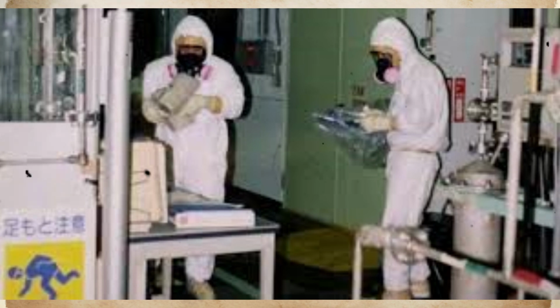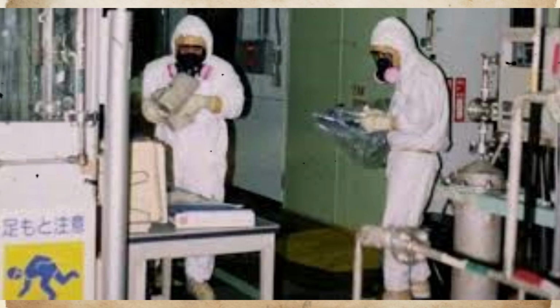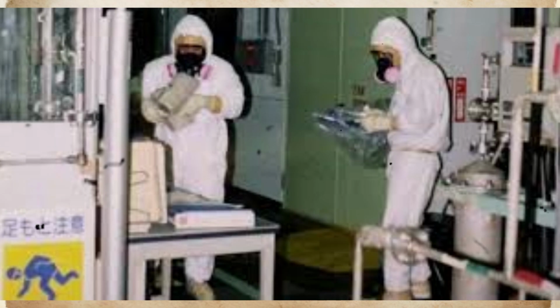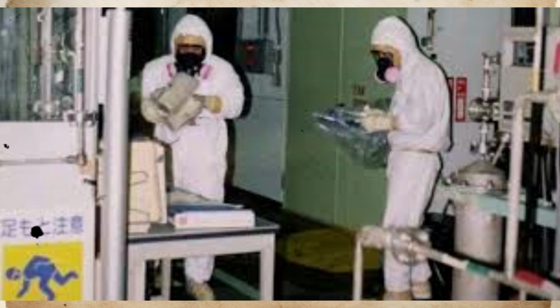Manual reactor depressurization was accomplished at approximately 9 on March 12 by using battery power to energize solenoid valves controlling safety relief valve operation. This required plant workers to carry automotive batteries from the plant parking area into the reactor building and connect them directly to valve control circuits using improvised wiring connections. The battery-powered valve operation successfully reduced reactor pressure from 7 MPa to approximately 0.8 MPa, enabling fire protection pumps to begin injecting water into the reactor vessel.